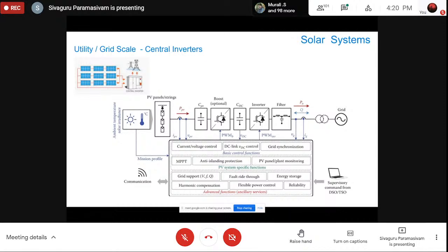If it is going to have 610 megawatt, the MPPT algorithm will tune the voltage accordingly. It will tell that, okay, the voltage is going in the right way. And if the 610 megawatt is going to go to 650 megawatt, fine. In the same profile, the MPPT will keep tuning the voltage. But when the 650 megawatt, for the reason of cloud coverage, suddenly falls to 600 or 550 megawatt, then the voltage will be adjusted within the inverter level, because the current is not in our control. Current is in the control of the sun.